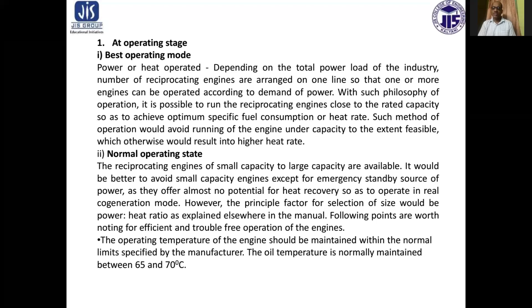First point: the operating temperature of the engine should be maintained within the normal limits specified by the manufacturer. The oil temperature is normally maintained between 65 to 70 degrees centigrade. Second point, prolonged overload condition on the engine should always be avoided. Unbalanced load condition should be limited so that rated current is not exceeded in any phase of the generator. Next point, it is desirable to provide suitable flywheel inertia to limit the cycle irregularity. It is desirable to maintain the engine speed at normal level. Sudden load imposition or shedding may abruptly change the speed and may damage some moving parts.